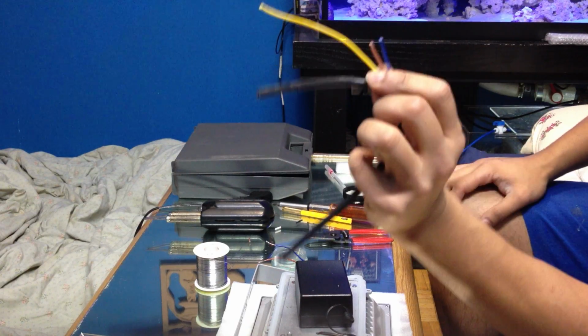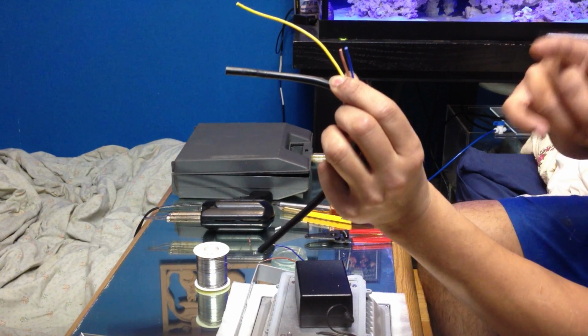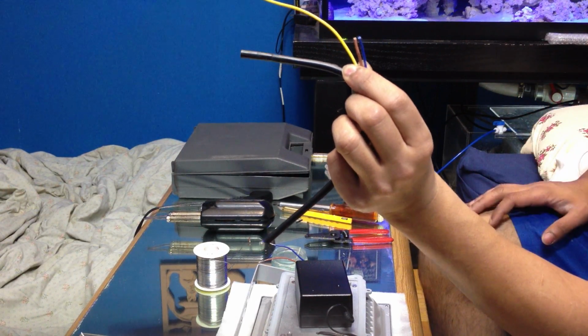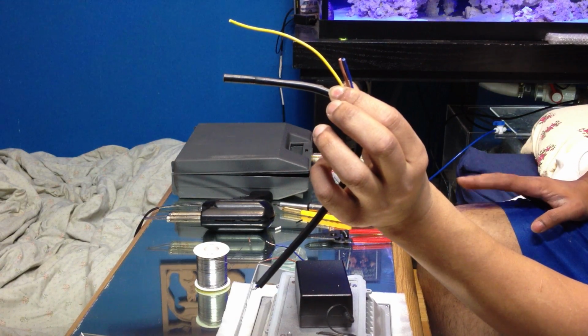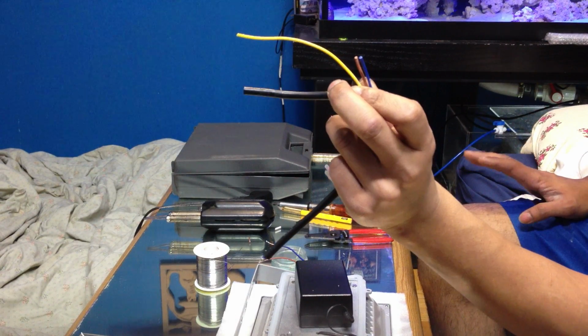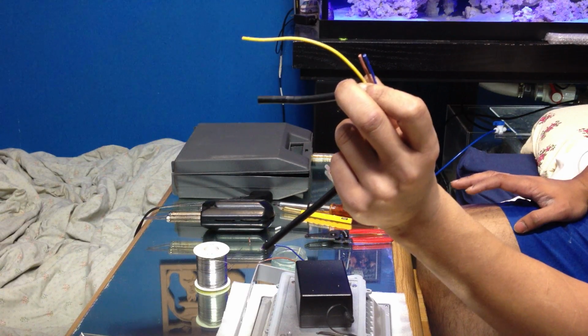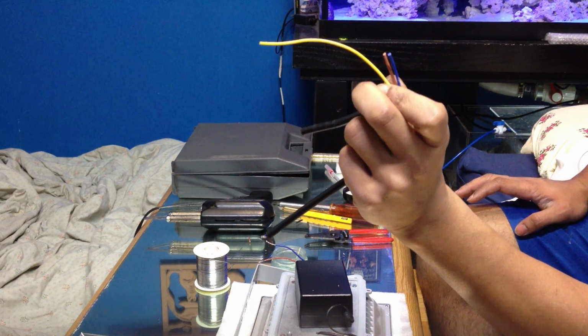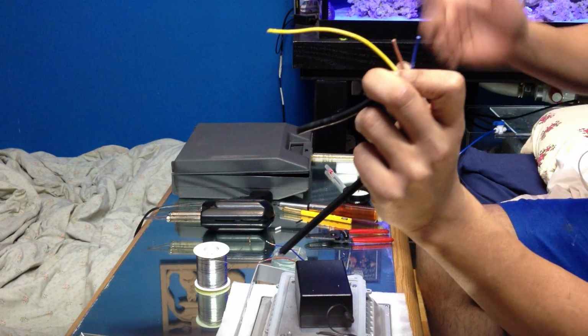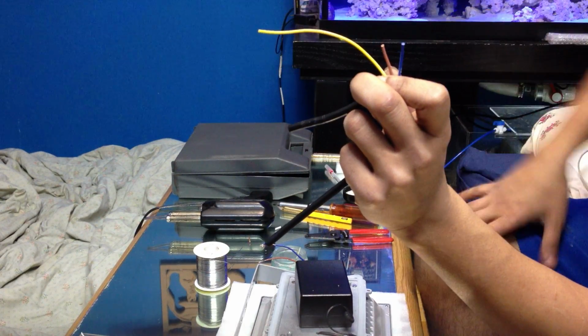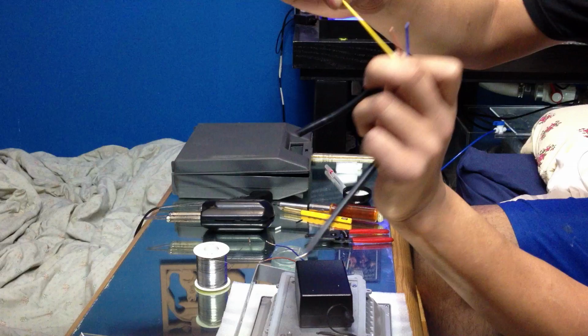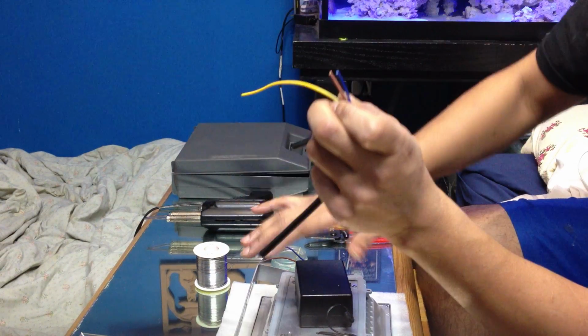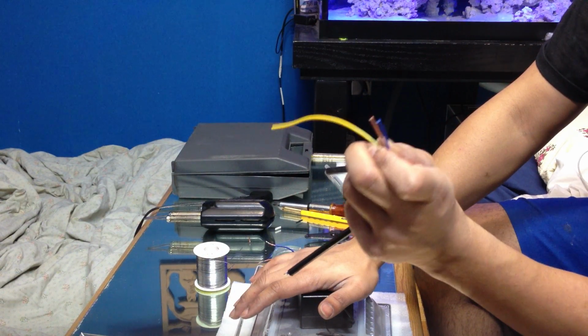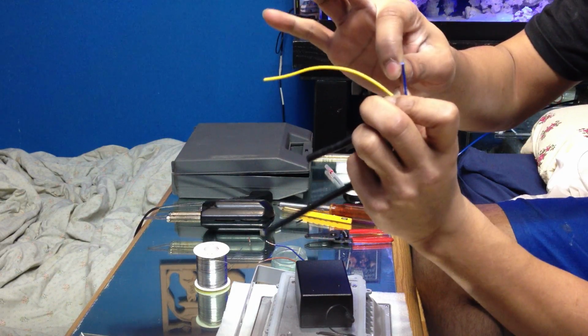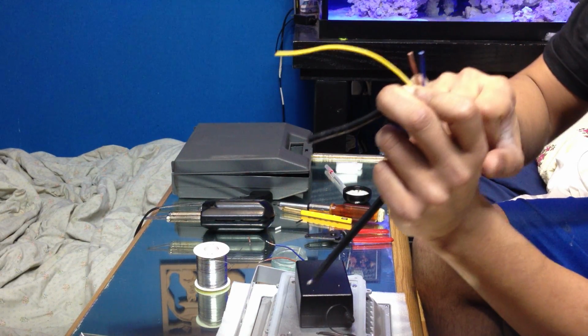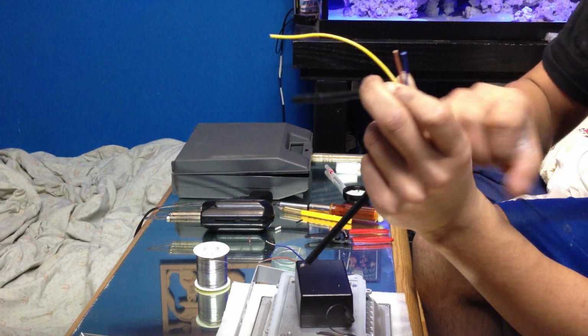Depending on what country you live in, you gotta double check exactly what type of wires or the terminals are in your wall socket and also your wires. This is coming from China, so in China, I'm assuming that this is the color code that they use. Yellow with the green stripe is always your ground. For those of you who are ordering this and installing these in Canada and the States, your brown is going to be your live, your blue is going to be your neutral.